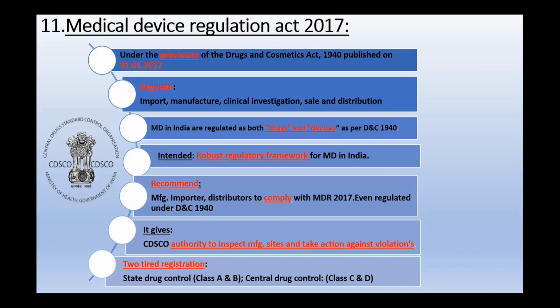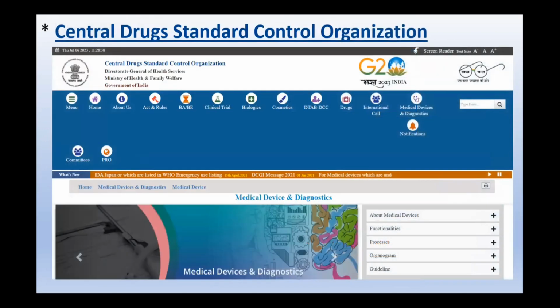The CDSCO has recommended that the manufacturer, importer, and distributor comply with the Medical Device Rules 2017, even when they are regulated under the Drugs and Cosmetics Act 1940. It gives the CDSCO the authority to inspect manufacturing sites and take legal action against violations. It also provides a two-tier registration system for medical devices, in the state and in the center. This is the website provided by the Central CDSCO for filing an application for approval to manufacture, import, or export medical devices.